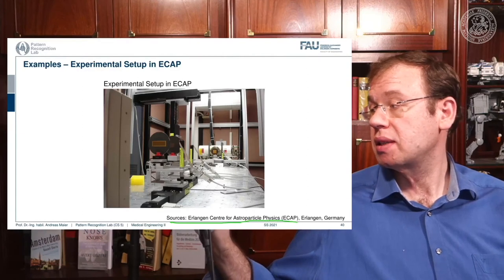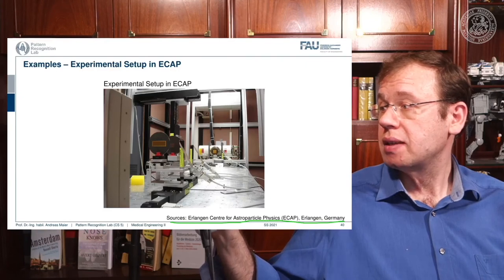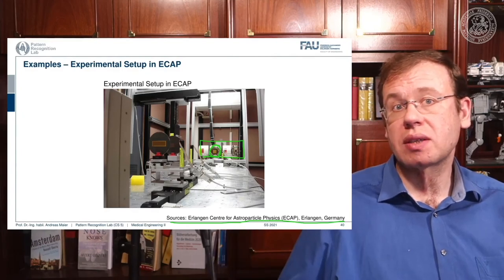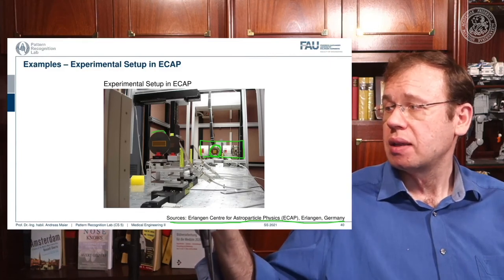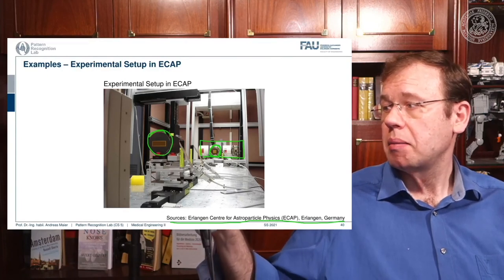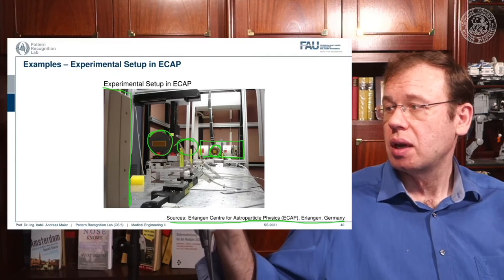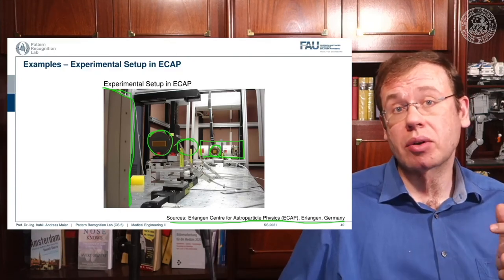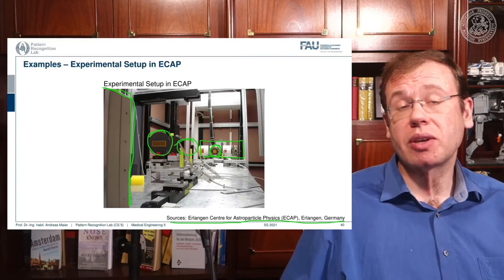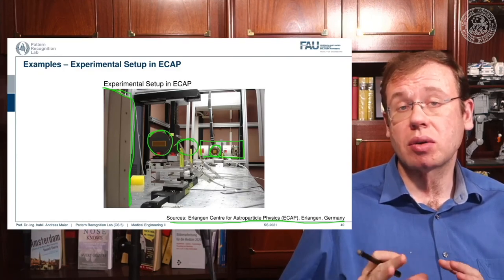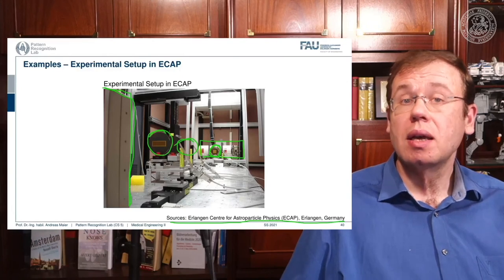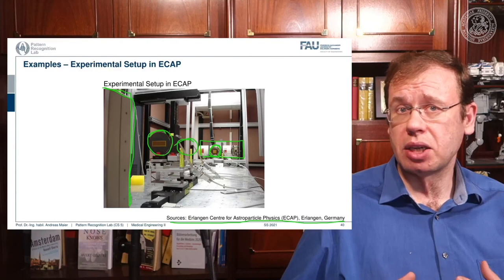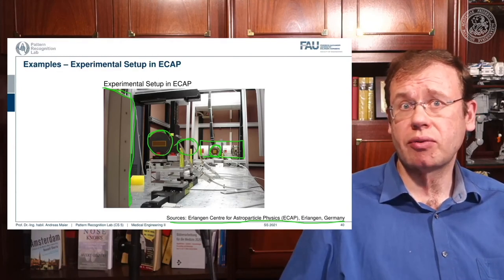The actual measurement setup is located at the Erlangen Centre for Astroparticle Physics in Erlangen, Germany. Key components: a medical-grade X-ray tube, the G0 grating for coherent source generation, the phase grating G1, the object placement area, and the detector with phase stepping. The long distances must be aligned to micrometer precision, requiring careful alignment and significant time investment. The setup may also be temperature-dependent, since micrometer-level thermal expansion can shift the gratings, requiring frequent recalibration — best done with automated means.